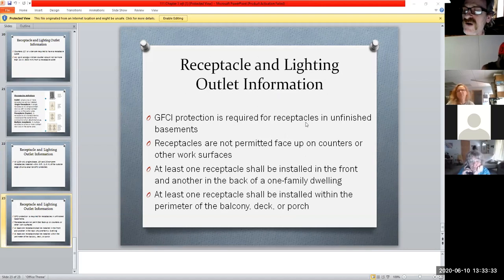GFI protection is required for all receptacles in unfinished basements because of flood factors. You cannot have receptacles installed into the cabinet with the face going up, with water being able to run into the receptacle. That's a huge no-no. Absolutely not. And at least one receptacle shall be installed. And remember, shall in the NEC's little library is absolutely must. Shall is their word, meaning you better do this. Shall be installed in the front and another in the back of a one family dwelling. What do they mean by that? That means on the outside of your house. You are required to have at least one receptacle front and back.